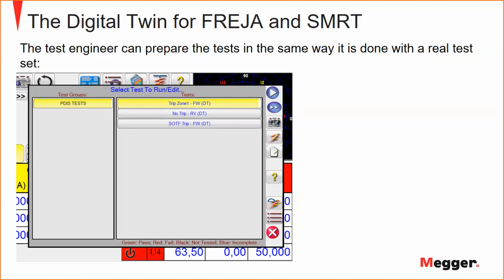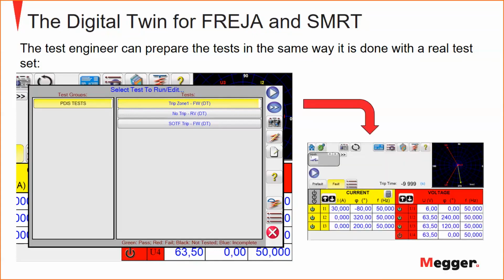So you prepare your test in the same way. I've done some examples. I've done a trip in zone 1, no trip in reverse, because I don't have any zone in reverse, and I have done a switch on to fault trip, like you do normally in FREJA and SMRT. And then you run them against the digital twin.